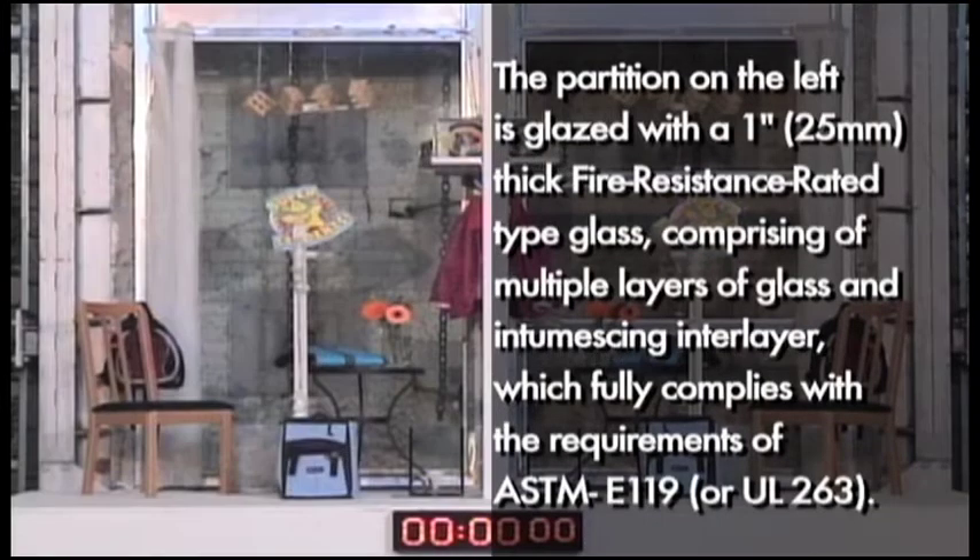The partition on the left is glazed with a one-inch thick, fire-resistance rated type glass, comprising multiple layers of glass and intumescent interlayer, which fully complies with the requirements of ASTM E119 (or UL 263).